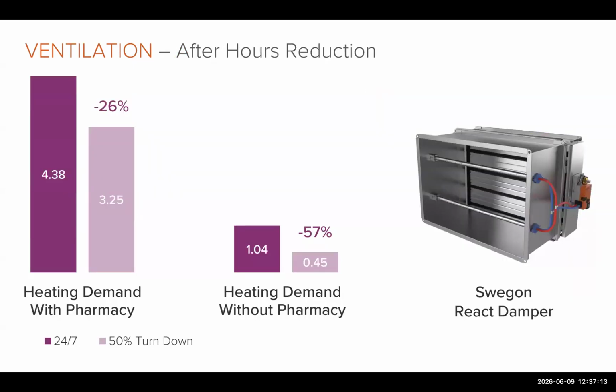In order to throttle down the system for the ERVs after hours, we used special smart dampers called react dampers. Those can be individually controlled. That resulted in a 26% reduction to the heating demand for the building as a whole. But to give you an idea of just how much the pharmacy ventilation affected things, if you take that pharmacy AHU out of the equation and just isolate the 4 ERVs, turning down that system after hours would reduce the heating demand by more than 50%.